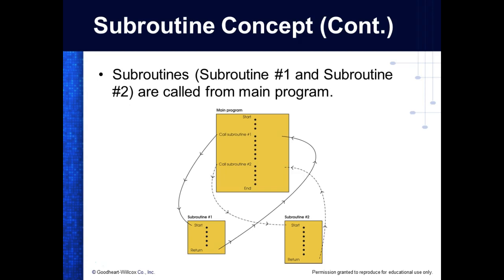So as soon as it sees a call, it saves the condition of the processor on the stack. Then it loads the counter with wherever the new subroutine is. Then it jumps down here. Then it runs the subroutine. And then when it sees that return, it tells it to pull all the information back off the stack. And where will it take it back to? It's going to take it back to the next instruction or the next rung after the JSR. And then it's going to start running the main loop again.